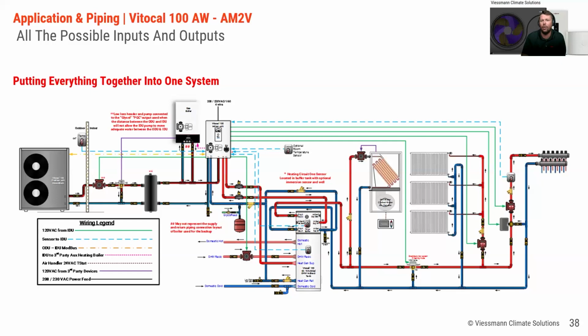It's just going to take a lot longer for that DHW tank to satisfy, potentially choking down the flow rate that you could achieve going to the DHW tank if they were completely separated. So I don't know if anybody else had that thought, but that's exactly why we show most of our drawings with the boiler in closely spaced tees between the indoor unit and the outdoor unit, because then it solves all those issues.